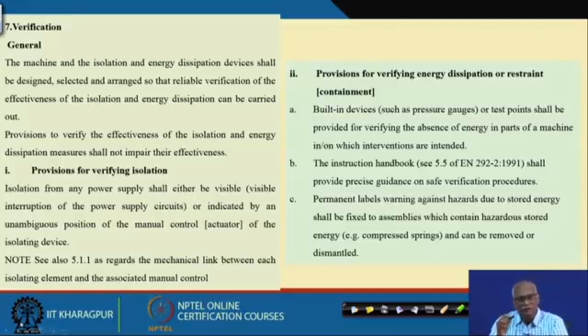Verification is very, very important. Everybody may say that they have put out the power, separated it, put the locks, put the tags, everything they have done. But it is very essential to check whether it is done properly. At the final place where people are working, you should be able to see that it is really done. There are many ways of verification. There are visible verifications, and built-in verification such as pressure gauges. If the pressure gauge shows zero, that means there is no pressure.